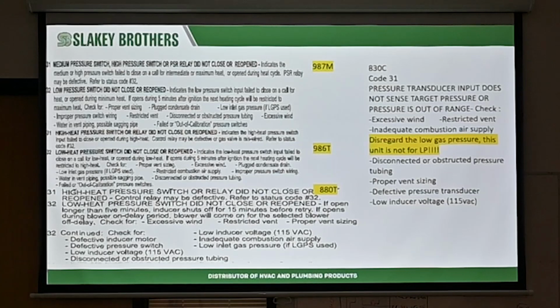And a lot of times that happens when we don't do the condensate drain right. When our condensate drain is not hooked up properly, the unit's not draining out properly, it's going to collect water in there. Water makes its way into the tubing. It stops the pressure, it stops the unit from working. And sometimes that water, because it's warm, because it was hot in there, could actually migrate up into the pressure switch and then ruin the internals of the pressure switch even after you fix the condensate drain. So just be careful on that one.